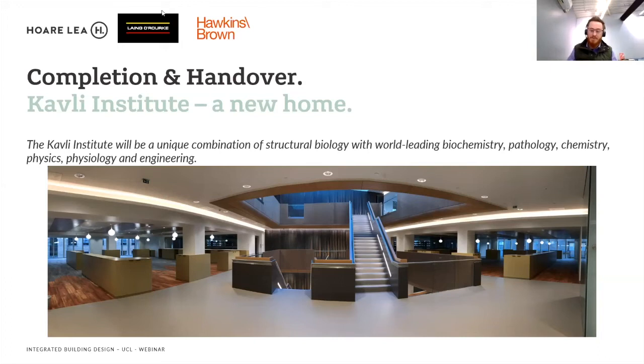In phase 1 they had individual air handling units per zone, lots of them dotted around the building. What we decided to do was pull them all together, as that isometric view showed, and have them stacked. Part of the reason was that when they all plug into a common vertical header, you can move the air around the building in a more flexible way.